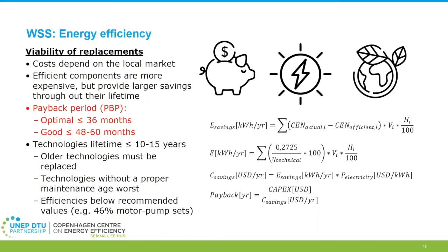This is a case study where the National Utility of Guyana, along with the Inter-American Development Bank, studied nationwide water utilities and identified a lot of potential because there were huge water losses happening, and they were incurring a lot of utility costs. They conducted energy audits and found a good number of energy efficiency savings with respect to improvement potential in power factors and the efficiency of water and motor pump systems. The average efficiencies were about 46%, which was quite low.